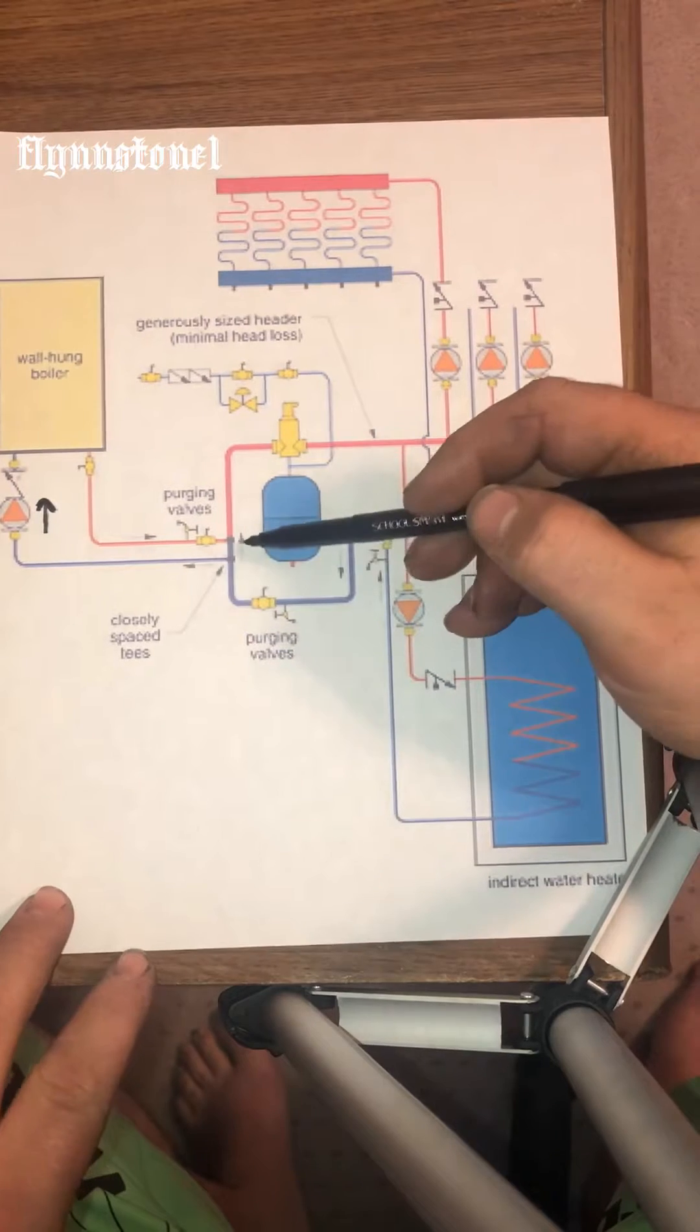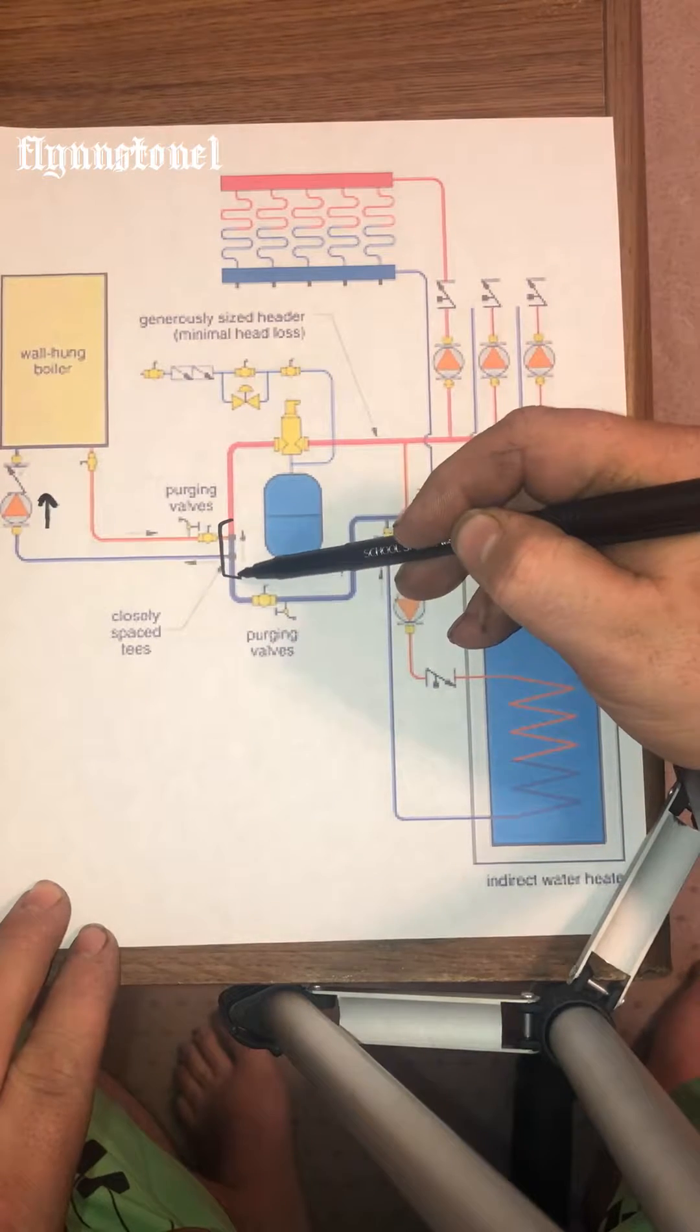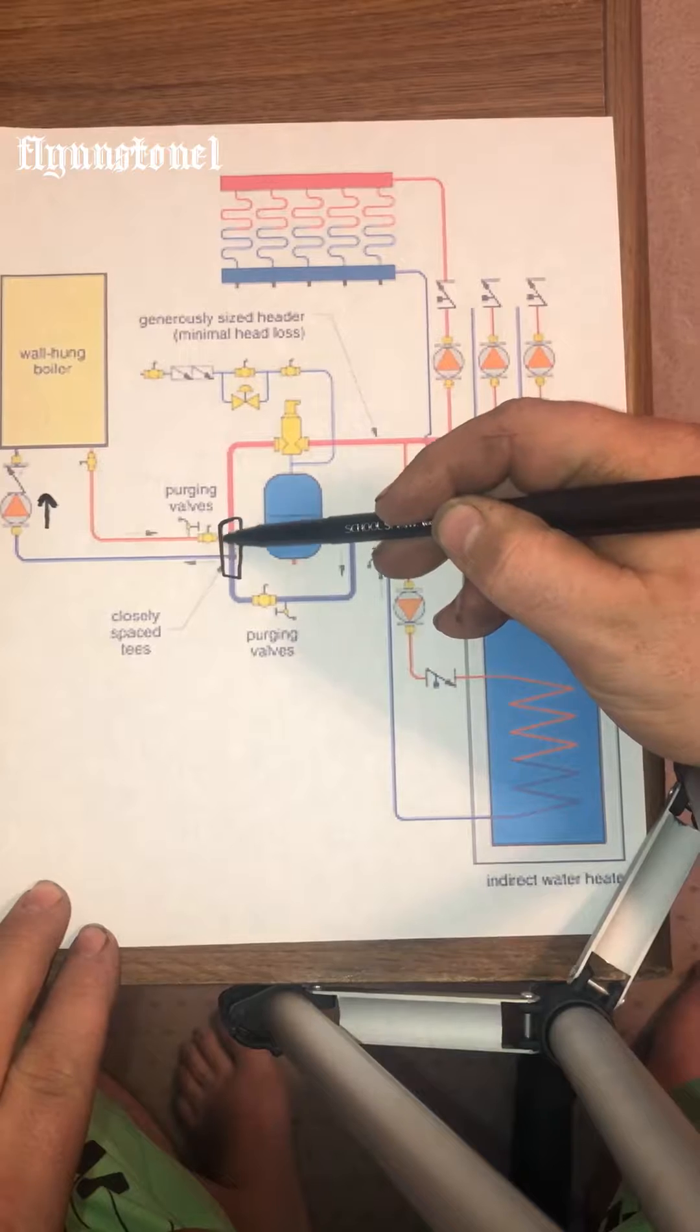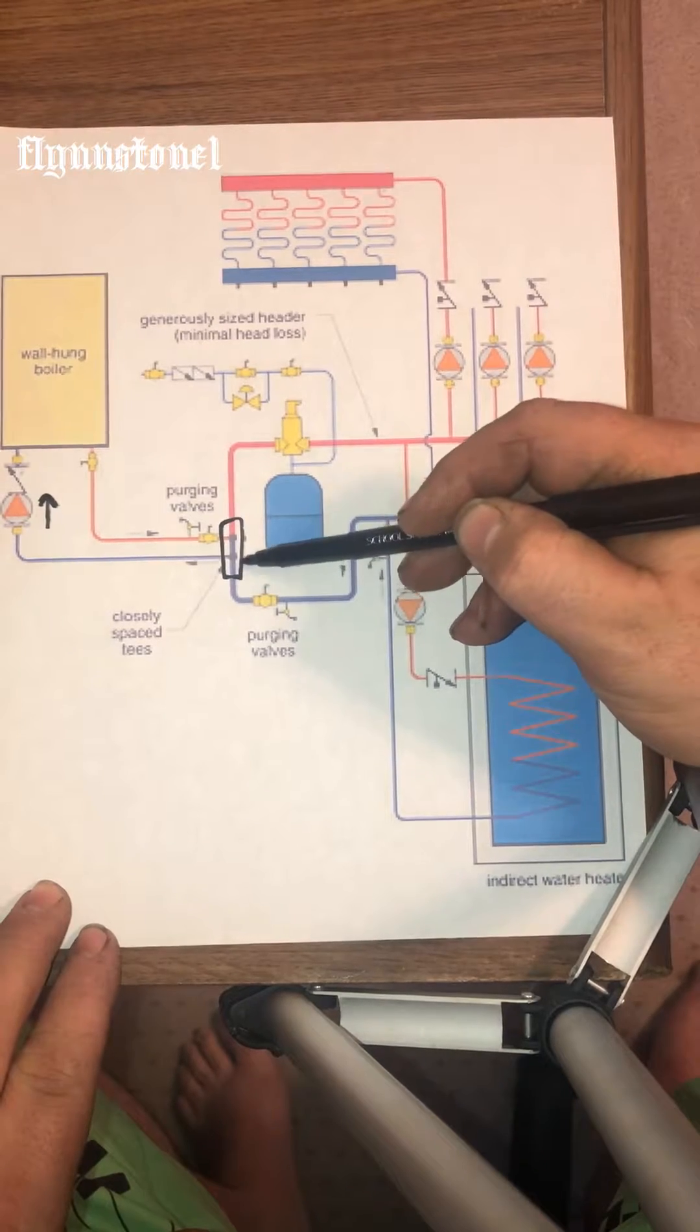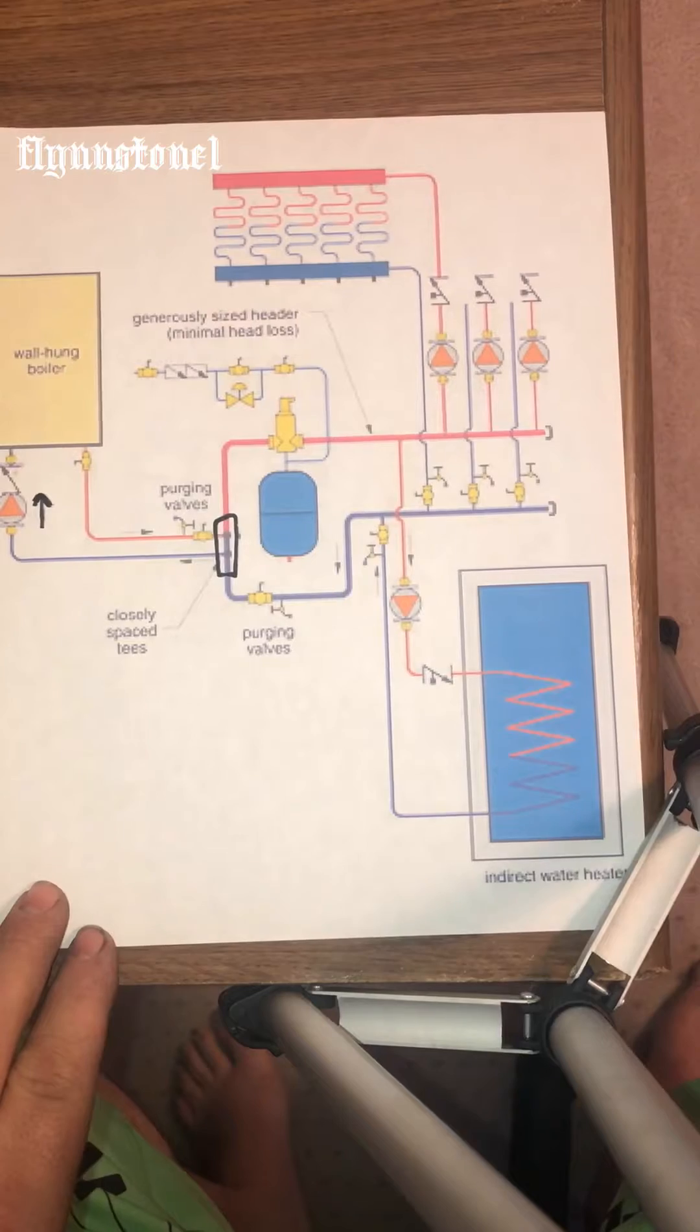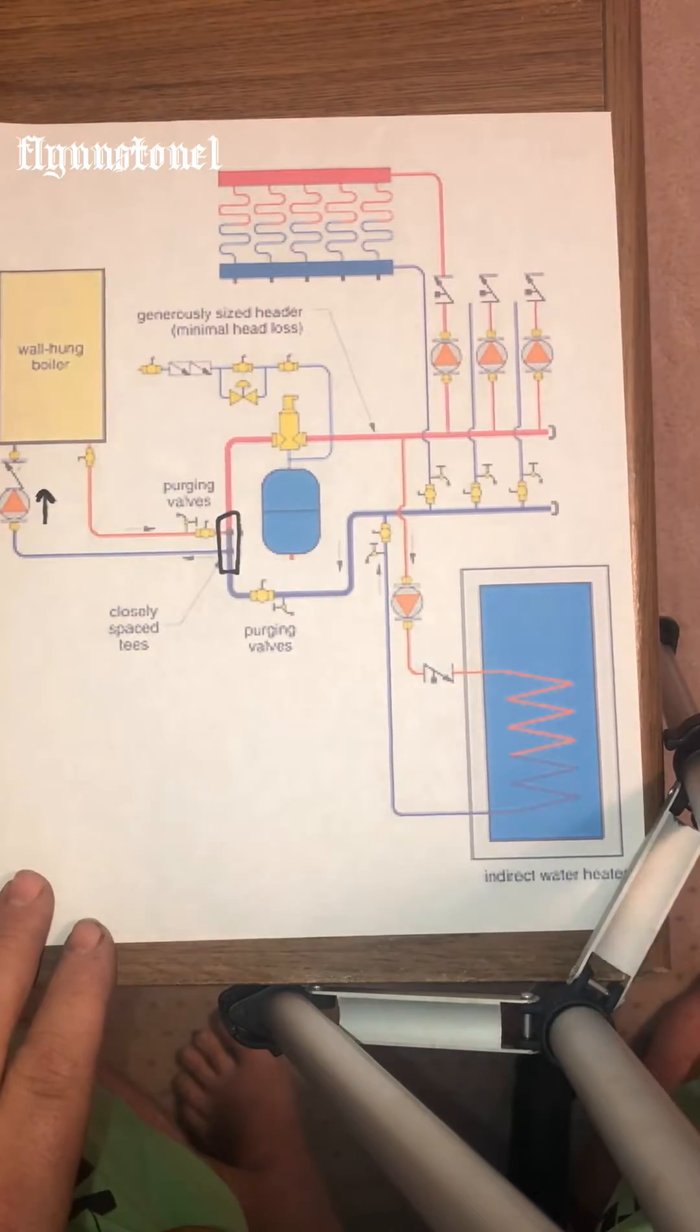Next you have your closely spaced T's and this is four times the diameter of the pipe max. Cannot go more.